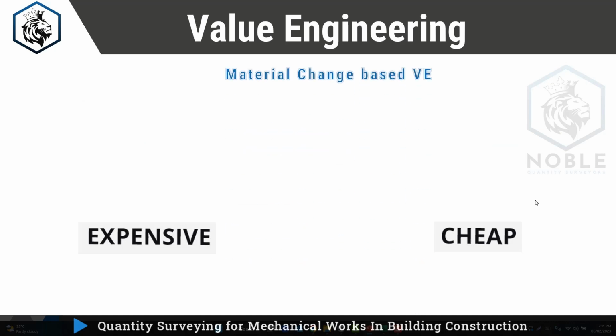The next one in material based value engineering is hydronic pipes. Hydronic pumps we have already seen, now we will see hydronic pipes. The expensive option is black steel seamless pipes. Whenever you see seamless pipes, it's an expensive option - this can be replaced with ERW. And if you see schedule 80, that means it's expensive pipe. Schedule 80 black steel seamless is not recommended for your building construction project, it is recommended only for industrial projects.